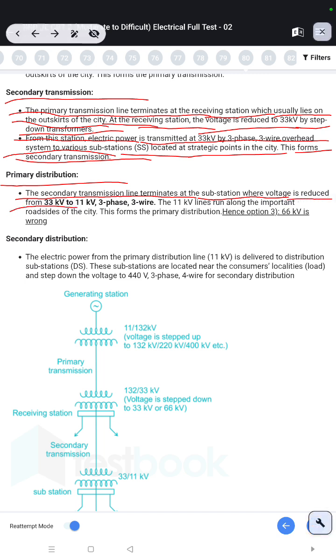Primary distribution: the secondary transmission line terminates at the substation where voltage is reduced from 33 kilovolt to 11 kilovolt, three phase three wire. The 11 kilovolt lines run along the important roadsides of the city. This forms the primary distribution.